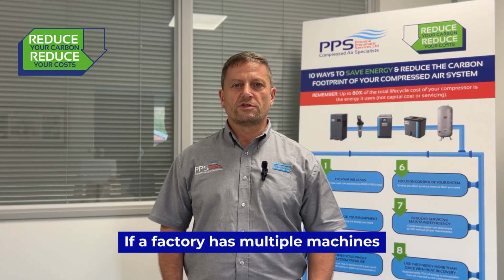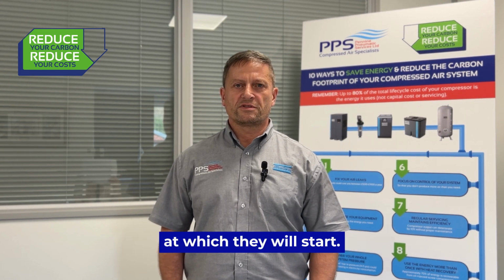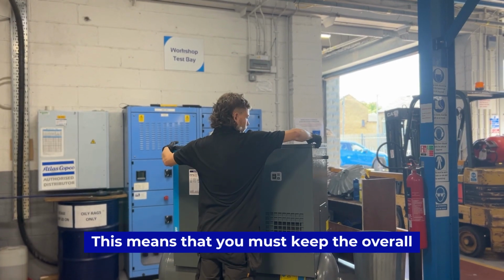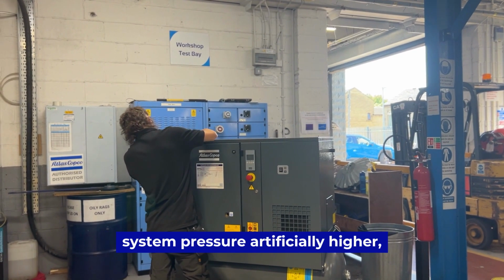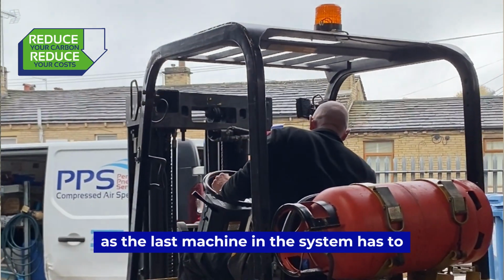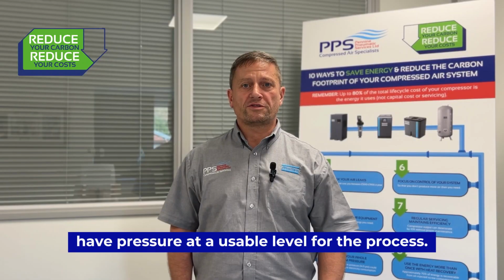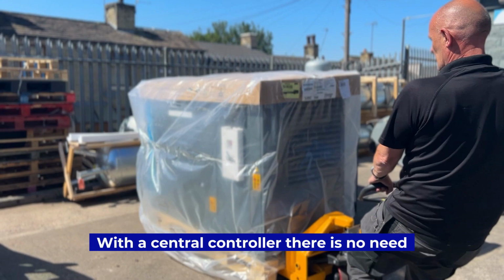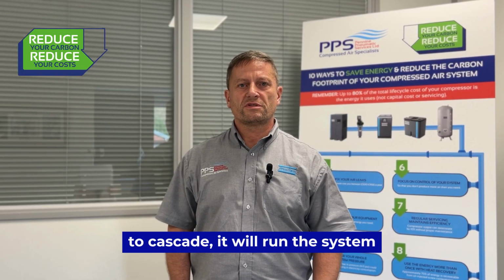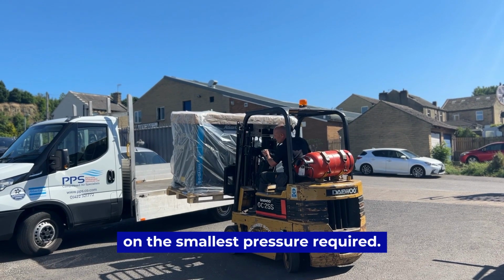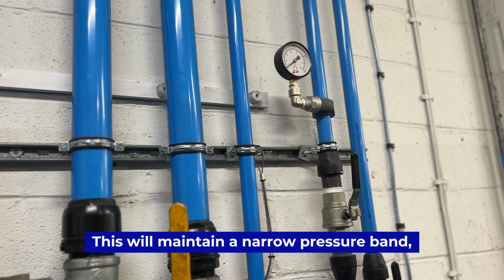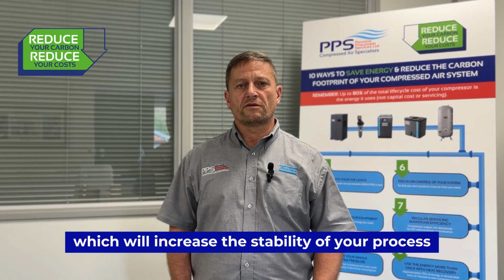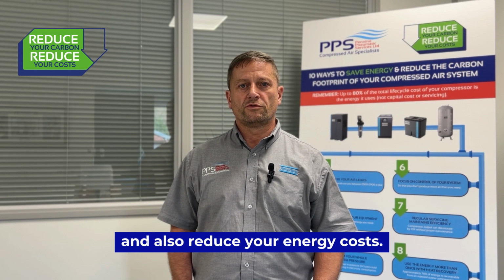If a factory has multiple machines without a central controller, you have to cascade the pressures at which they will start. This means that you must keep the overall system pressure artificially higher, as the last machine in the system has to have pressure at a usable level for the process. With a central controller, there is no need to cascade. It will run the system on the smallest pressure required. This will maintain a narrow pressure band, which will increase the stability of your process and also reduce your energy costs.